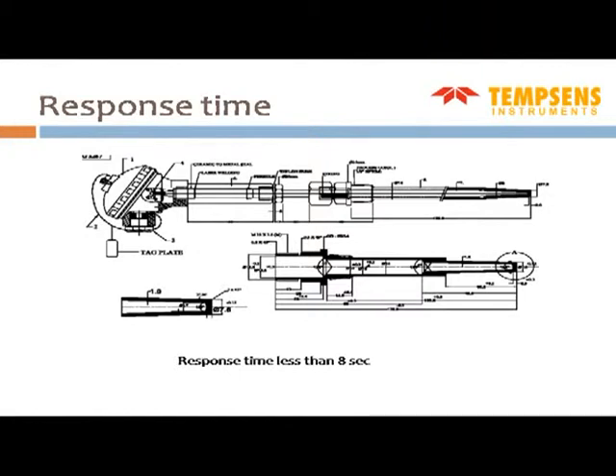This is typically for Nuclear Power Corporation, NPCIL. We made a special thermowell. You can see the tip is tapered. This is an RTD, and a thermocouple is a point type of sensor, whereas an RTD is a sensor with a particular length. For example, an RTD may be 20 millimeter long, and so it senses through a length of 20 millimeter. So we have a taper drill in the thermowell, and the insert is made of silver, which is also tapered. So it is touching throughout the length of the thermowell from inside. You have better contact, and better contact translates into better response time. In this thermowell, the response time was less than 8 seconds.